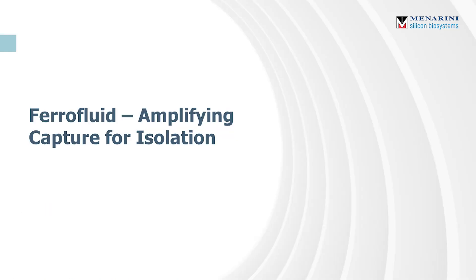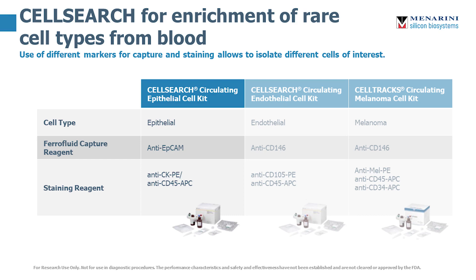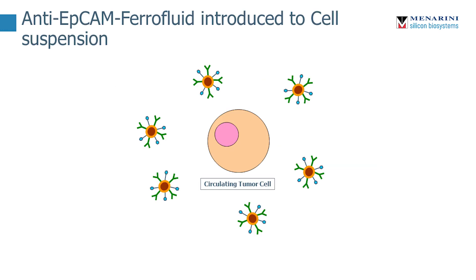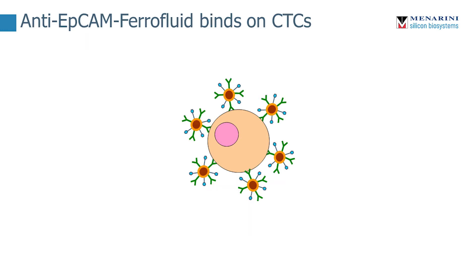Now I'd like to address ferrofluid. The CellSearch platform uses a ferrofluid that amplifies capture of cells for enrichment and isolation. CellSearch has a variety of kits and we use different ferrofluids to target different chemistries and different cell types. When we use these different markers in conjunction with our ferrofluids, we can more closely define a population of cells and understand how they contribute to a phenotype. The ferrofluid itself is an iron nanoparticle with a polymer layer. We then conjugate an anti-EpCAM antibody and a biotin analog to create a snowflake shape. When an anti-EpCAM ferrofluid is introduced to a cell suspension — whole blood, cerebrospinal fluid, et cetera — the ferrofluid will bind to any EpCAM present on those circulating tumor cells or other EpCAM positive cells.